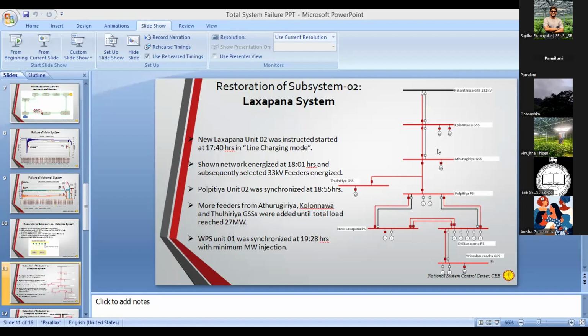Then some of the feeders will be switched off. You know there are 33 kV feeders in this substation. Those feeders will be switched off. Another thing you have to understand is that it is just a single machine, not like the previous system with so many generators. With only a single machine, its inertia is very small, so the frequency is going to fluctuate quickly. Therefore you have to switch on the 33 kV feeders one by one. You can't energize all of them at once. You switch on one feeder, wait until the frequency settles down, and then switch on the next one. Like that, you gradually load the generator.